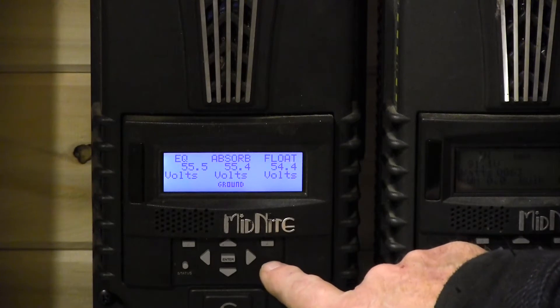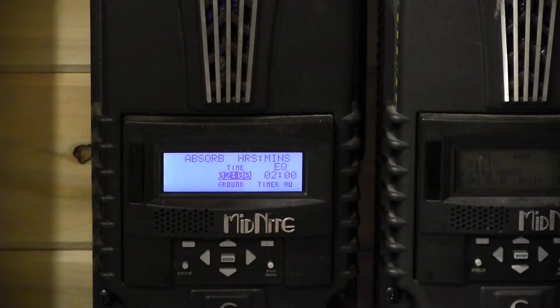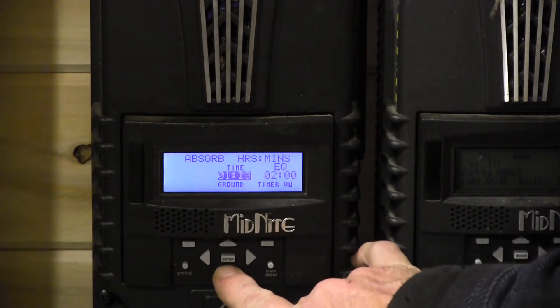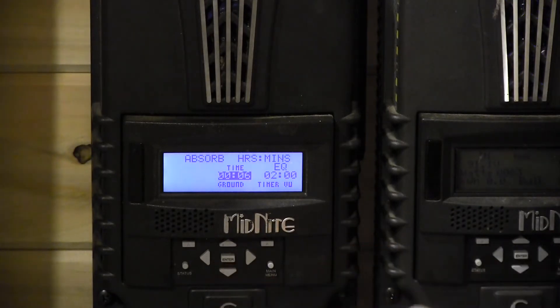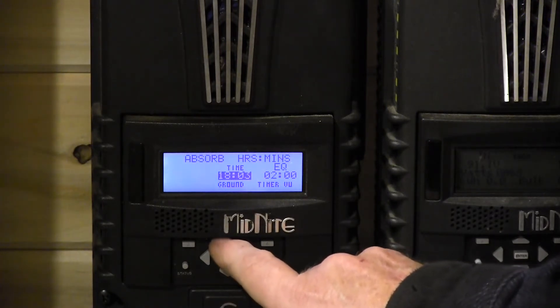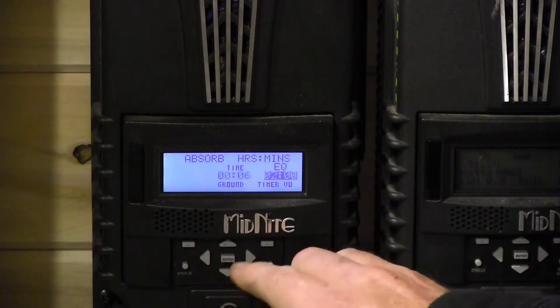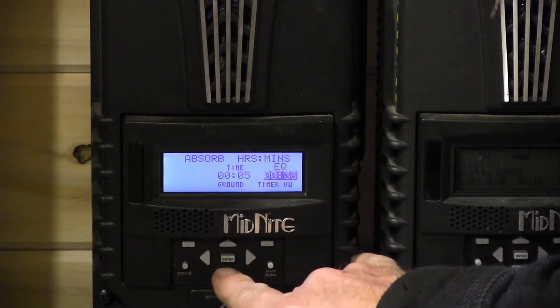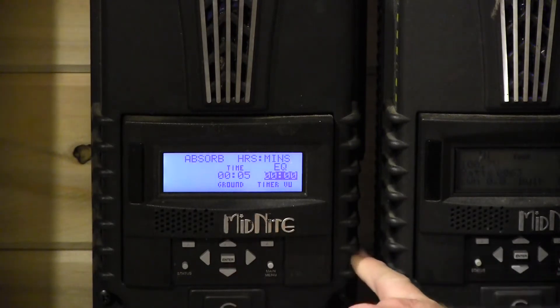We save by pressing the Enter button in the middle, then press the main menu button to back up. Now we go to Charge Time using the right arrow. They want six minutes of Absorb time — the Classic goes down to a minimum of five minutes, so six is fine. We'll run it down so you can see: below five minutes it jumps to 18 hours, so the minimum Absorb time is five minutes. We set it for six as requested. We then run Equalize time down as low as it'll go — that goes to zero — and save.